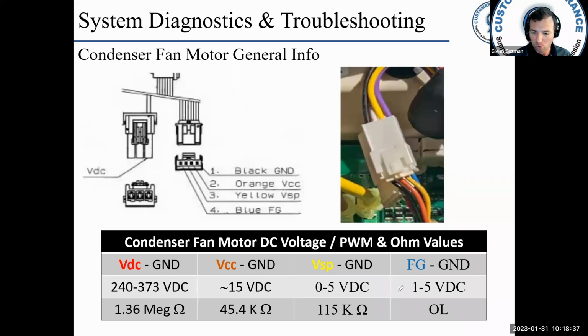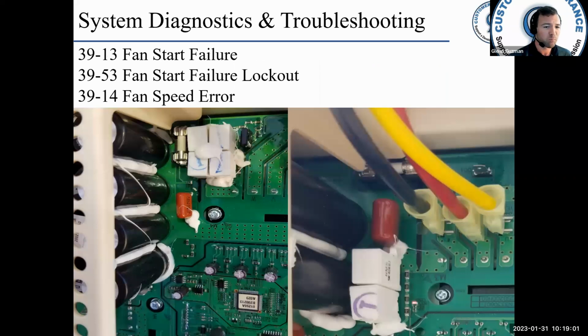If your ohm readings and voltage readings vary, then concerning voltage, I would look at what faults are there. If you have everything disconnected and you're ohming the motor itself, then you could have a bad motor, or a failed motor, I should say. It's not bad, it's failed. Now, a couple of fan motor faults: 3913 fan start fault, 3953 fan start failure lockout, and 3914 is a fan speed error. One thing we need to remember is there is a replaceable fuse on these VFDs or inverters, if you will.